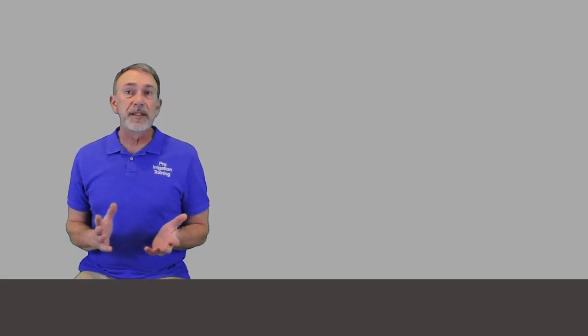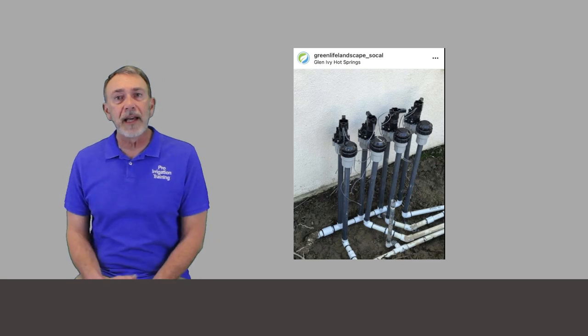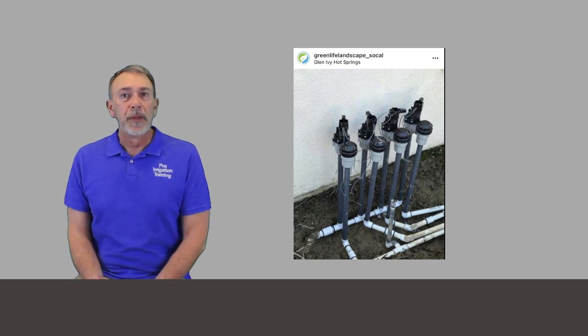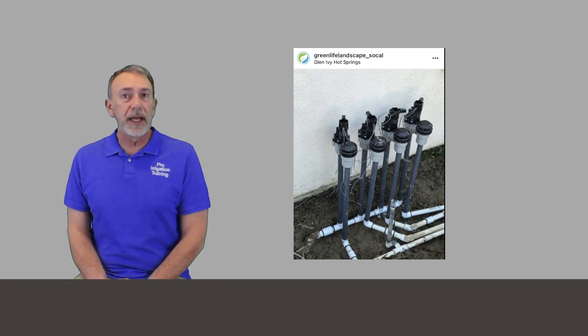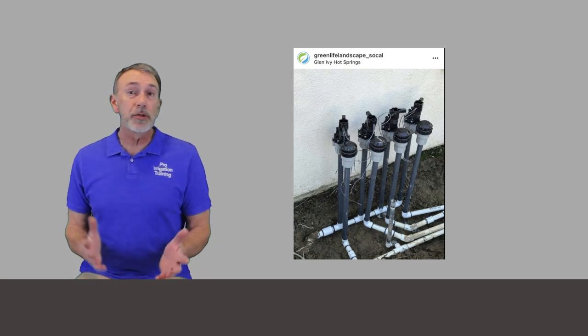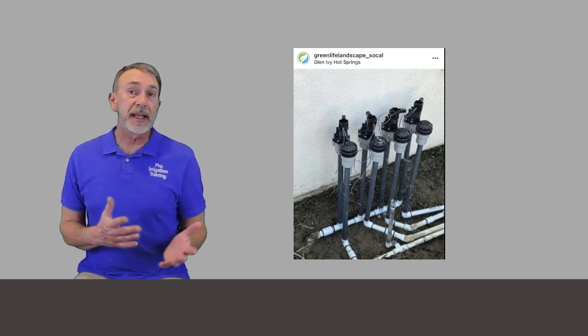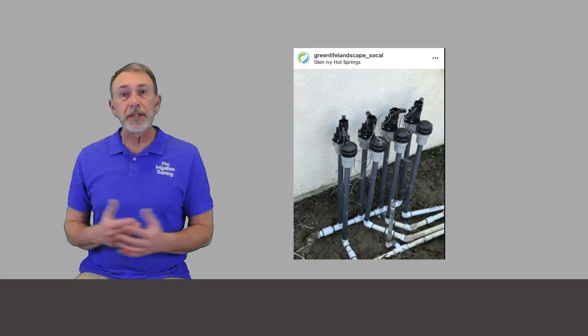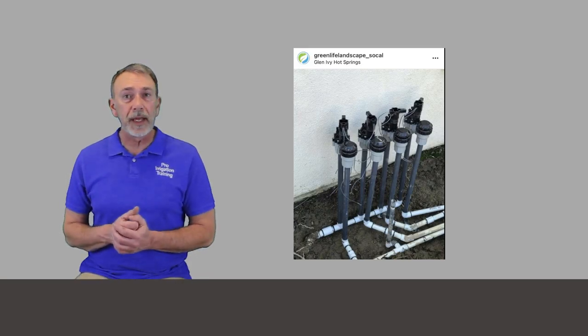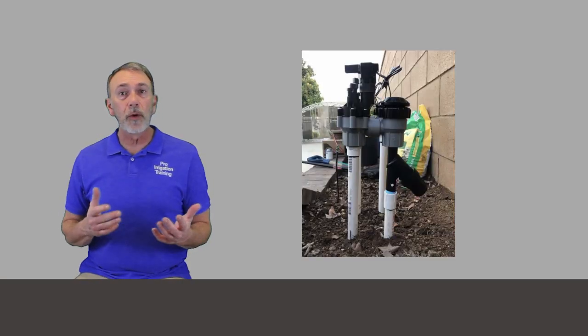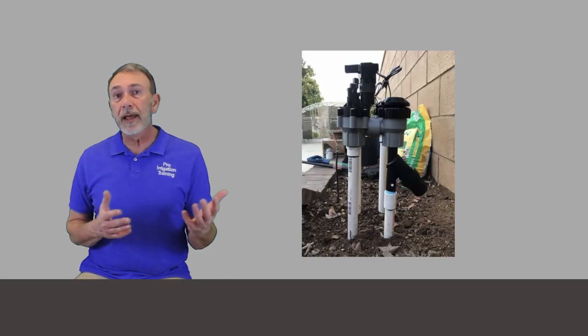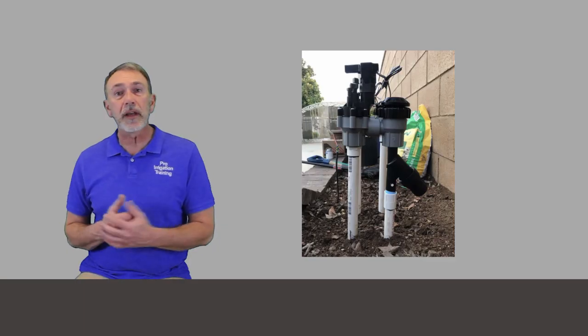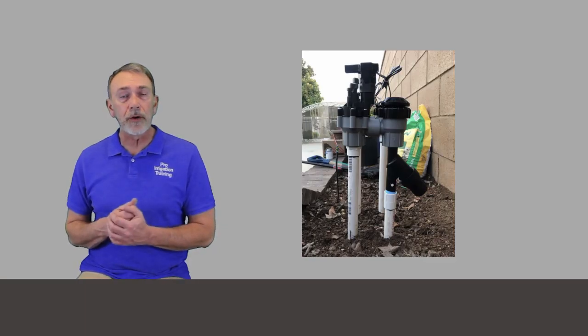So if you had a shutoff valve on the exit side of it, it would just push water as it was running. It would push water back up and open the vent up immediately and just rush water out around the device. So where you're going to see these though, is the anti siphon valve. A lot of places exclusively use these anti siphon valves, which is a combination product between a solenoid valve and an atmospheric vacuum breaker.